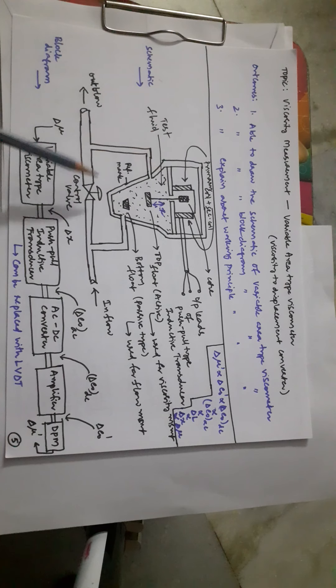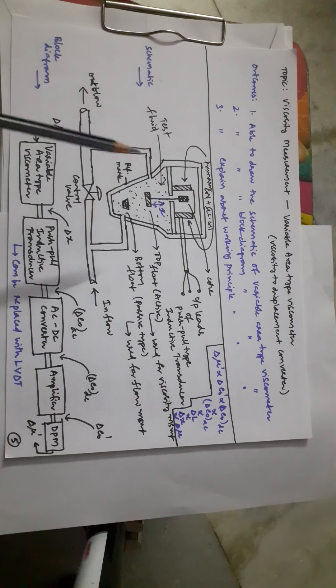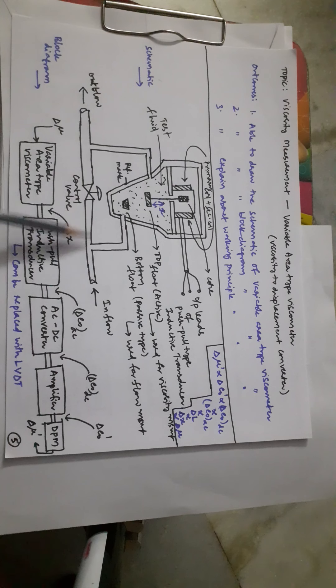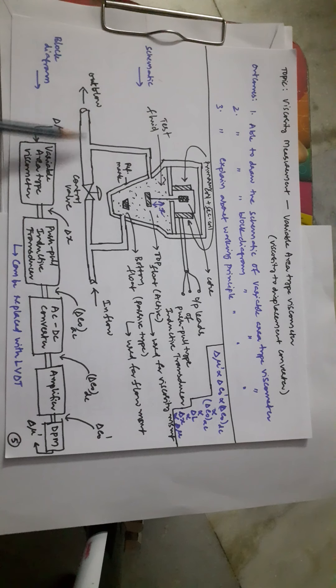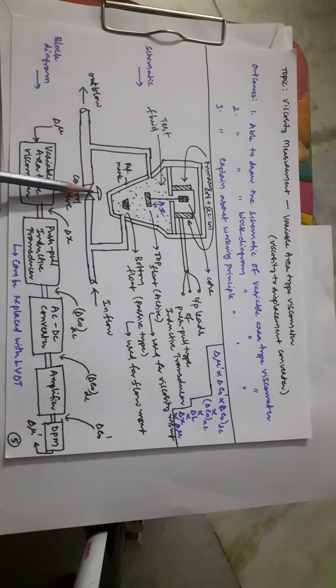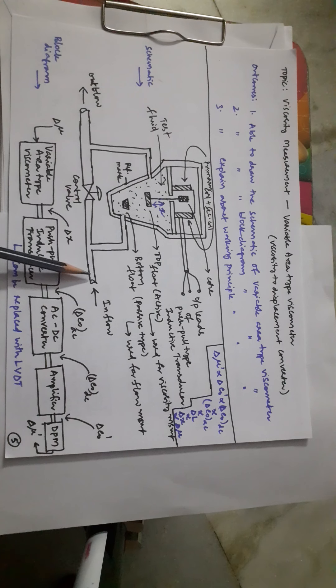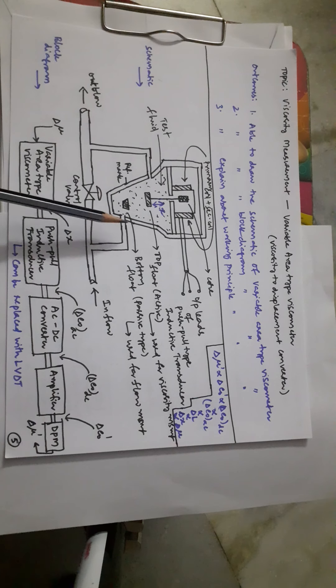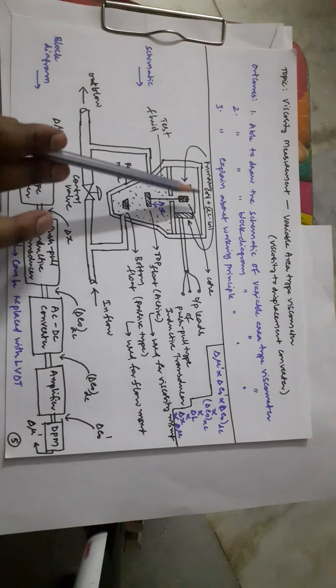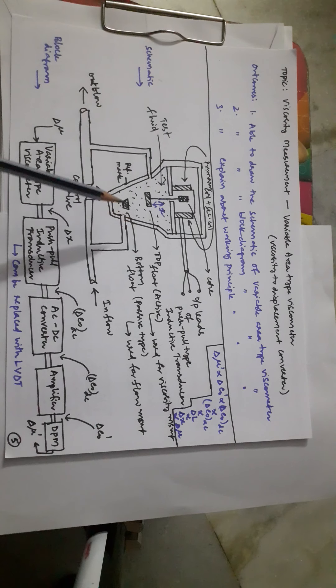This is the schematic of the variable area type viscometer. There is an inlet flow and an outlet flow — a fluid whose viscosity is to be measured passes through a flow pipeline. To control the flow rate, a control valve is used. Opening or closing this control valve varies the output flow rate with respect to the input flow rate.